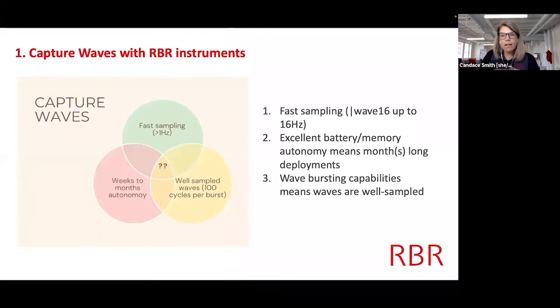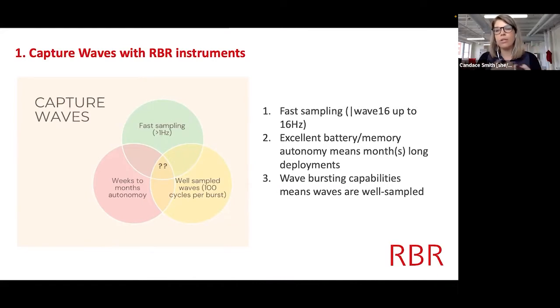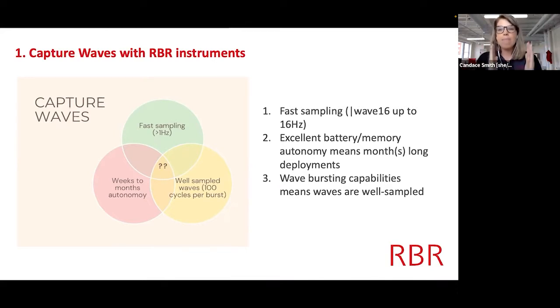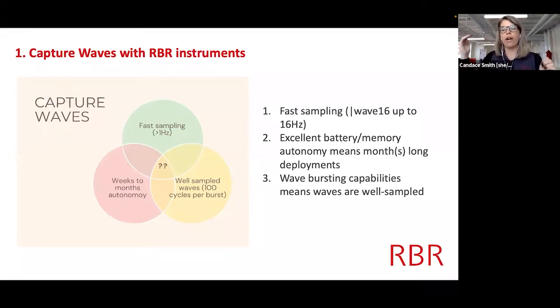At RBR, we can capture waves because we have these three intersections. Any RBR instrument essentially can do this. We do have fast sampling — with the Wave 16 feature, you can get up to 16 Hz sampling and 16 Hz bursts. There's excellent battery and memory autonomy, which means you can get months-long deployments. And we have this wave bursting capability — you measure waves by bursting on, sampling quickly, and repeating that cycle over and over.